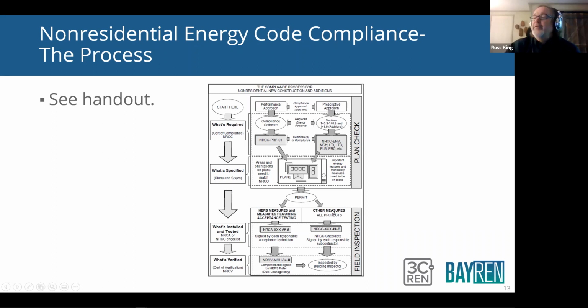The stuff that's verified by the building department just gets checked on the NRCC forms, the checklist, and the building inspector does that. But there's a lot of measures that have to be tested, either by a third-party inspector like a HERS rater, or by a certified person, which can be the installer, so they can test their own work, but they have to be certified. Those are called acceptance tests. And that's kind of like forcing commissioning to happen, sort of the traditional definition of commissioning, where you actually test a building before people occupy it.